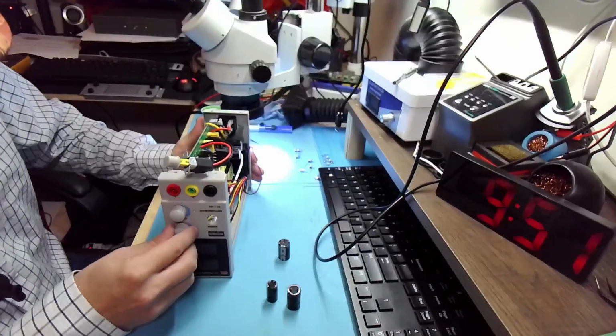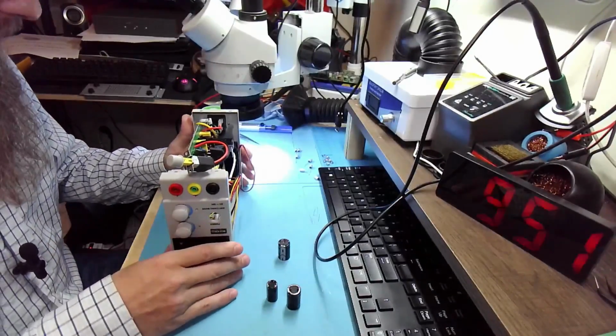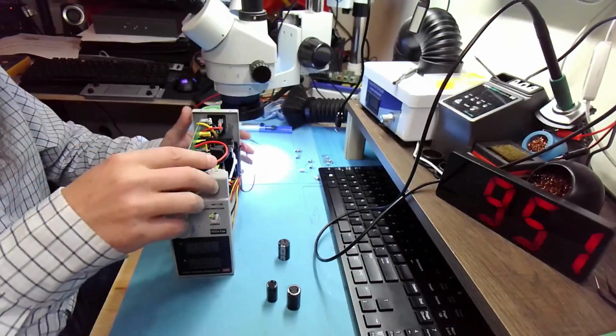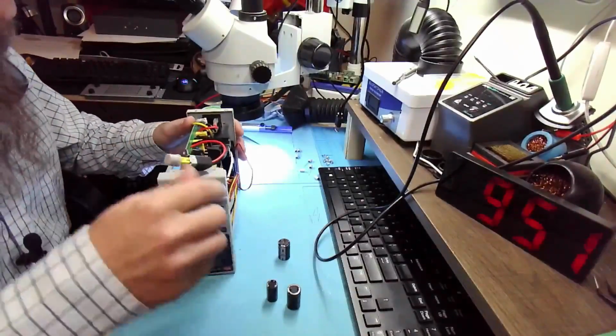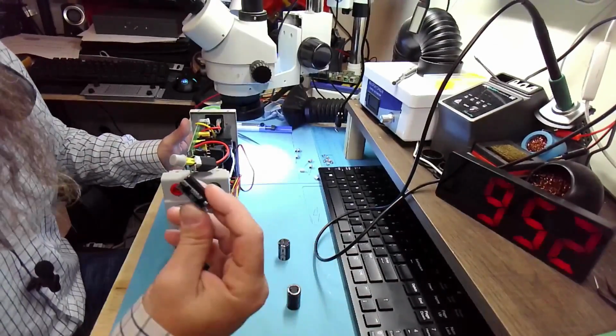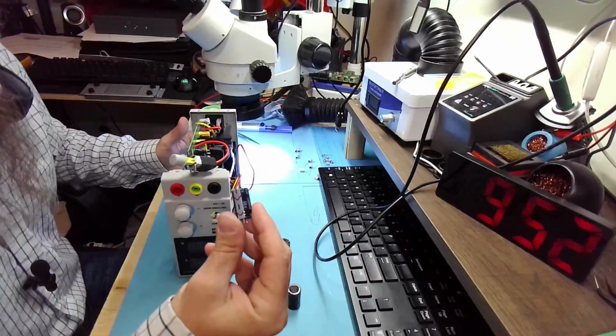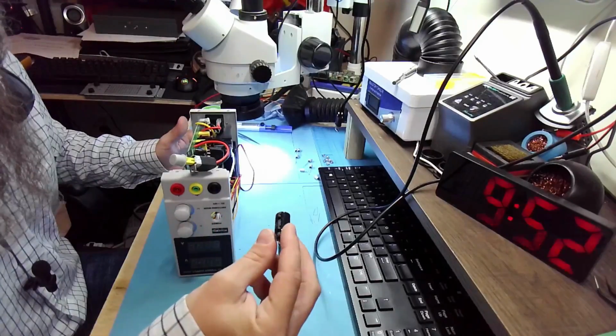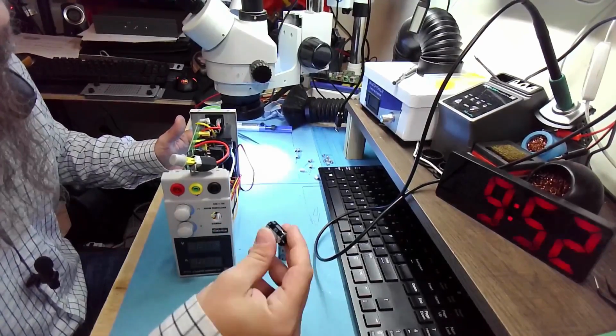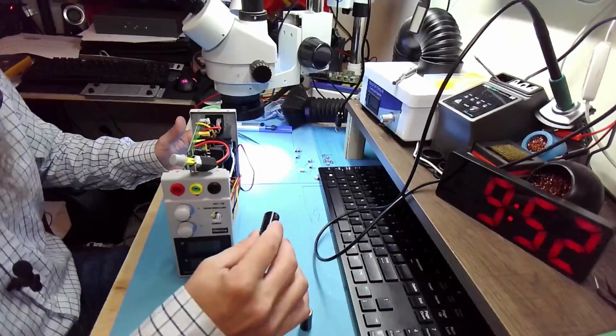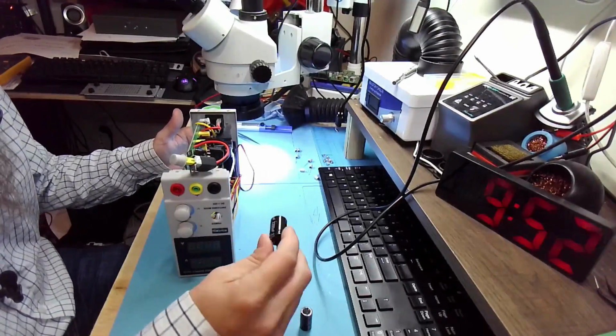And so we need to be careful about what voltage we produce with it. But just to check that this will resolve the problem. So this one measured 300 microfarads instead of 1000. So low reading means most likely it's dry. We can open it and actually check.